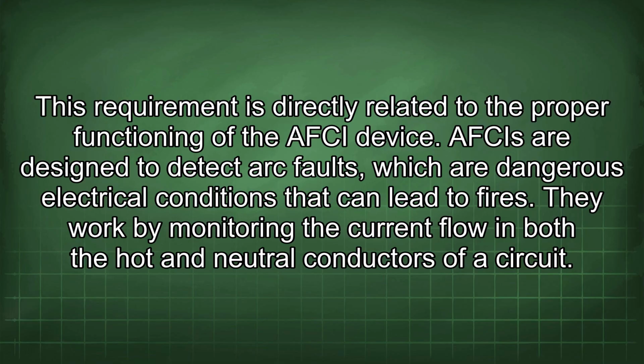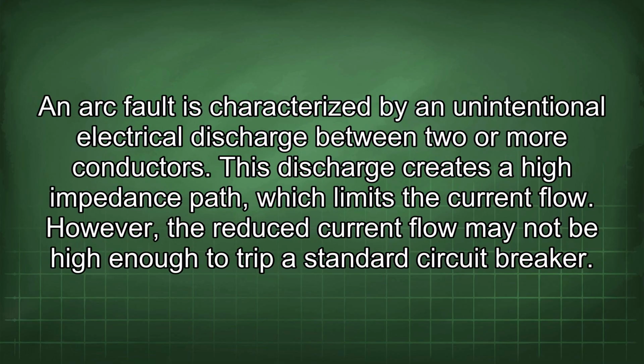AFCIs are designed to detect arc faults, which are dangerous electrical conditions that can lead to fires. They work by monitoring the current flow in both the hot and neutral conductors of a circuit. An arc fault is characterized by an unintentional electrical discharge between two or more conductors. This discharge creates a high impedance path, which limits the current flow. However, the reduced current flow may not be high enough to trip a standard circuit breaker.